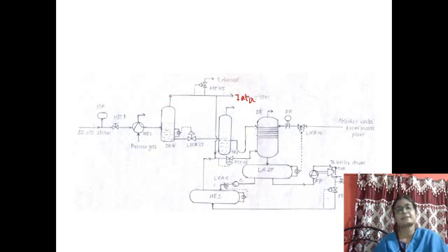For the outgoing pressure line, it should be maintained strictly at the 7 atta steam line. We may restrict the output flow to this level also, but if the steam line gets affected, that will be transferred to the deaerator and will in turn affect the ultimate process. So this should be air failure to open type.